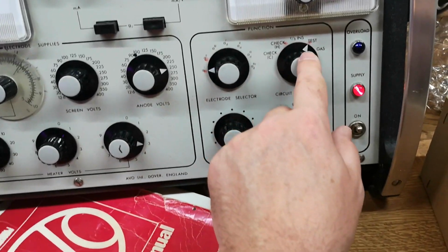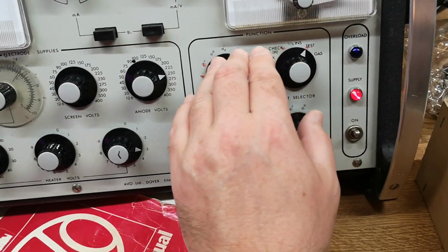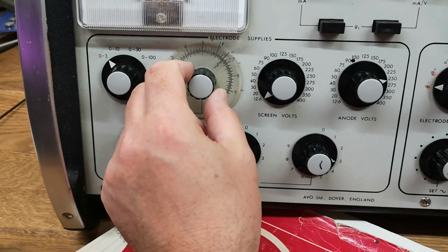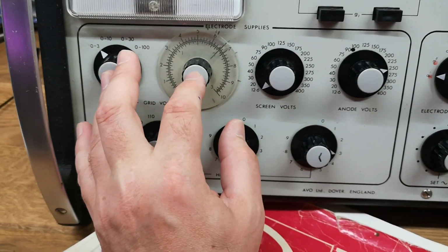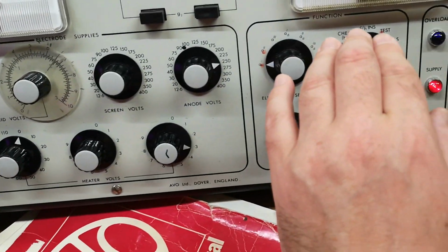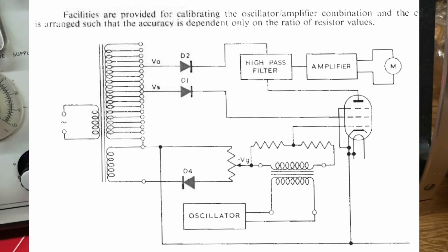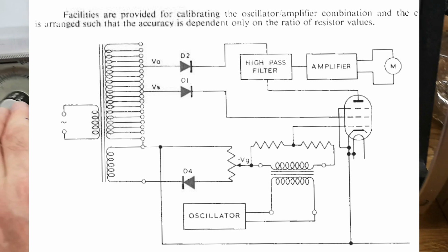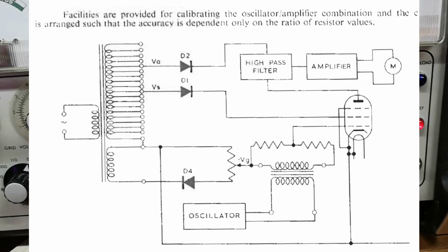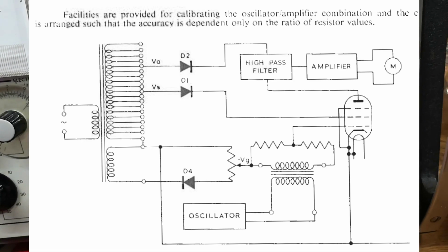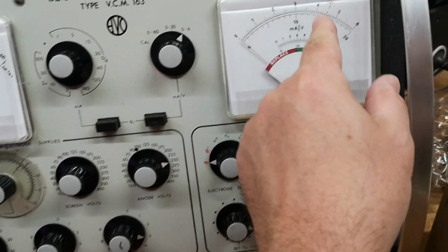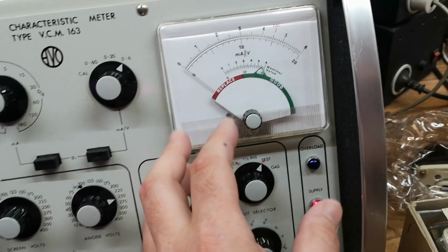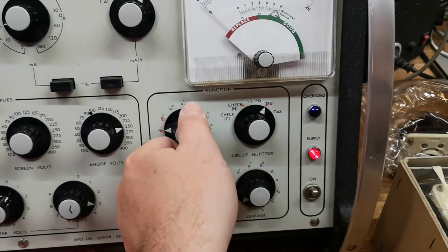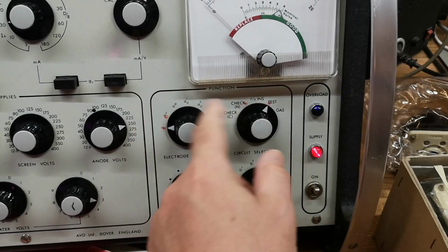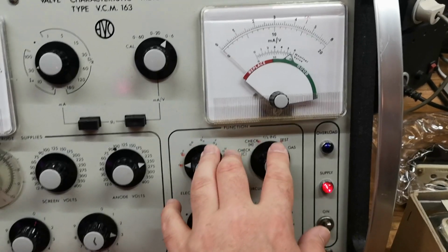For an ECC81, what I've set up right now, it will apply an AC signal into your control grids. So there's a 2 volt DC negative voltage, but there will now be a very weak AC voltage from an oscillator applied to the grid. That AC volt will of course be gained to the anode, and then the anode AC will be amplified and read out on the display, and this is your gain. So that is how it works, and you can change between the 2 different anodes, and then you'll read your 2 different gains if it's a dual triode.